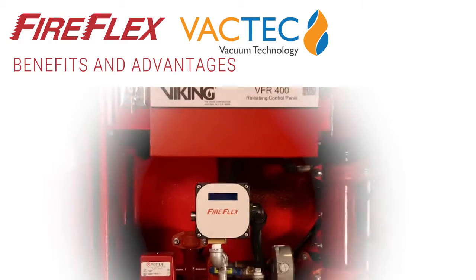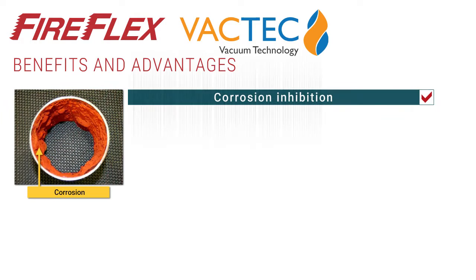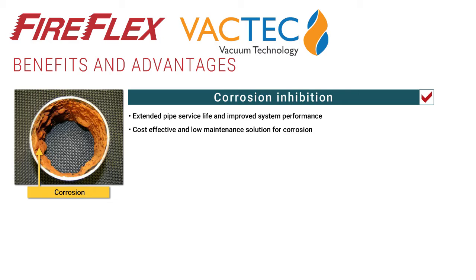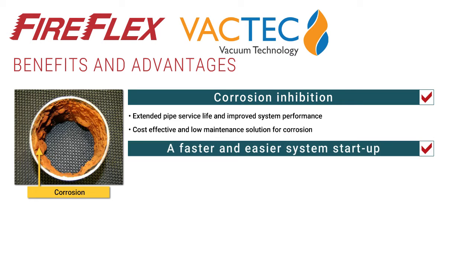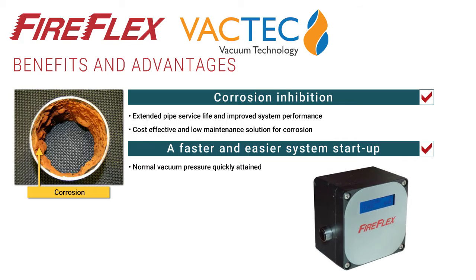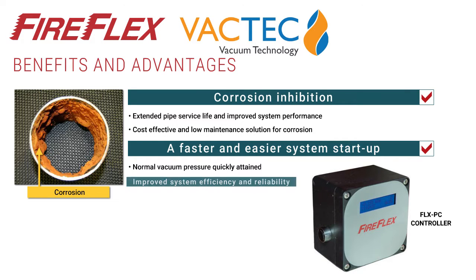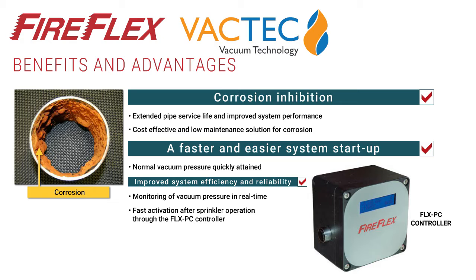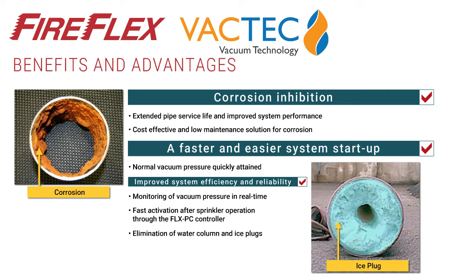The benefits and advantages are the following. Corrosion inhibition enables extended pipe service life and improved system performance. It is a cost-effective and low-maintenance solution for corrosion. Ease of operation and maintenance permits to quickly attain normal vacuum pressure. An improved system efficiency and reliability permits the monitoring of vacuum pressure in real time, a fast activation after sprinkler operation through the FLX PC controller, the elimination of water column and ice plugs, and a uniform filling of piping and water delivery.